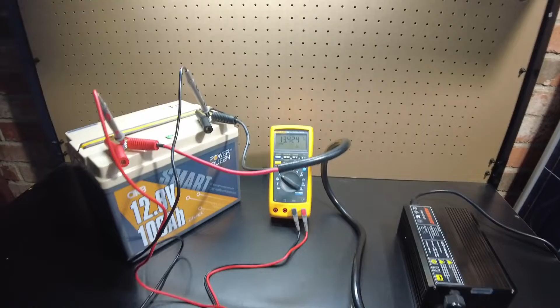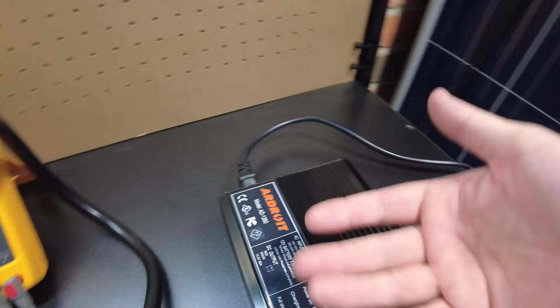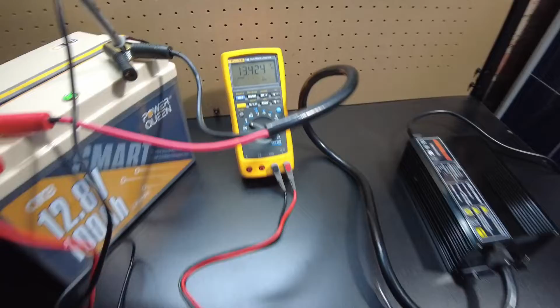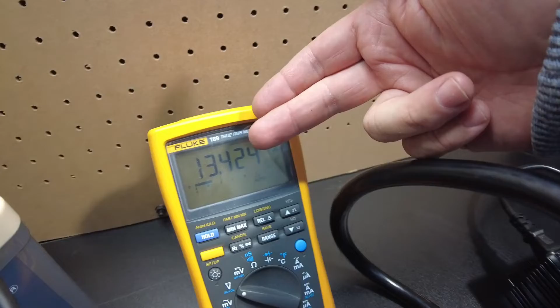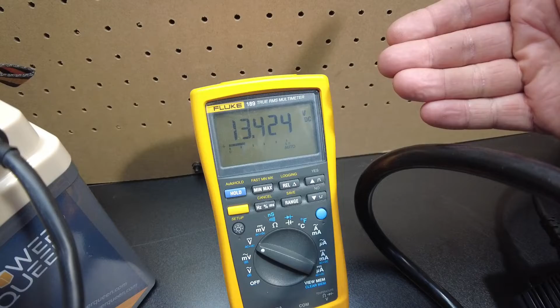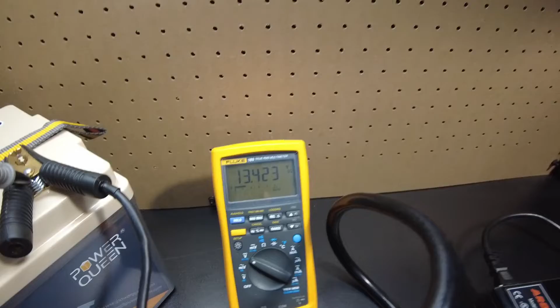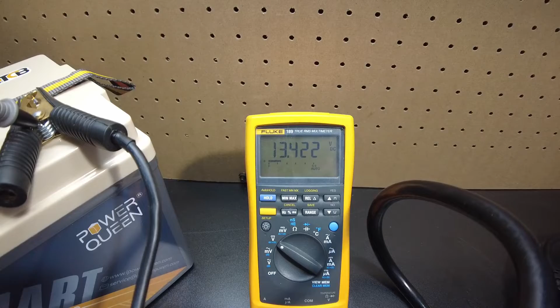Alright, the charger shut down, and it's been resting for a little bit after that. We're currently resting at 13.4 volts. Now I want to turn the charger back on and see what it actually charges up to. Does it charge up to the 14.4 volts plus or minus 0.2 stated in the manual? I'd like to see it at least get to 14.2, but preferably 14.4 and possibly 14.6. That will tell us how well the cells are balanced and how well they're matched.